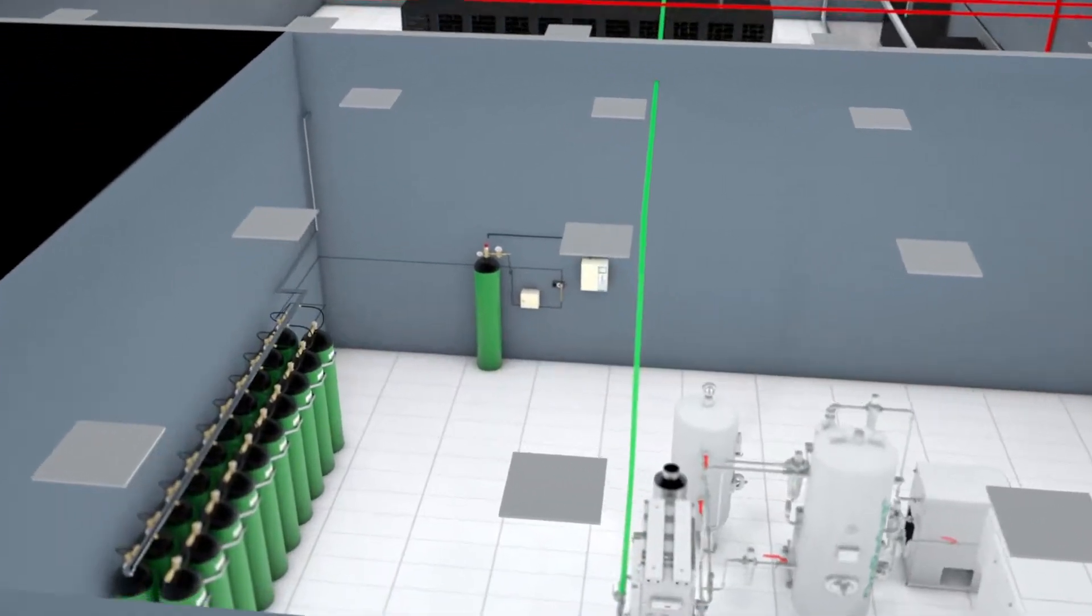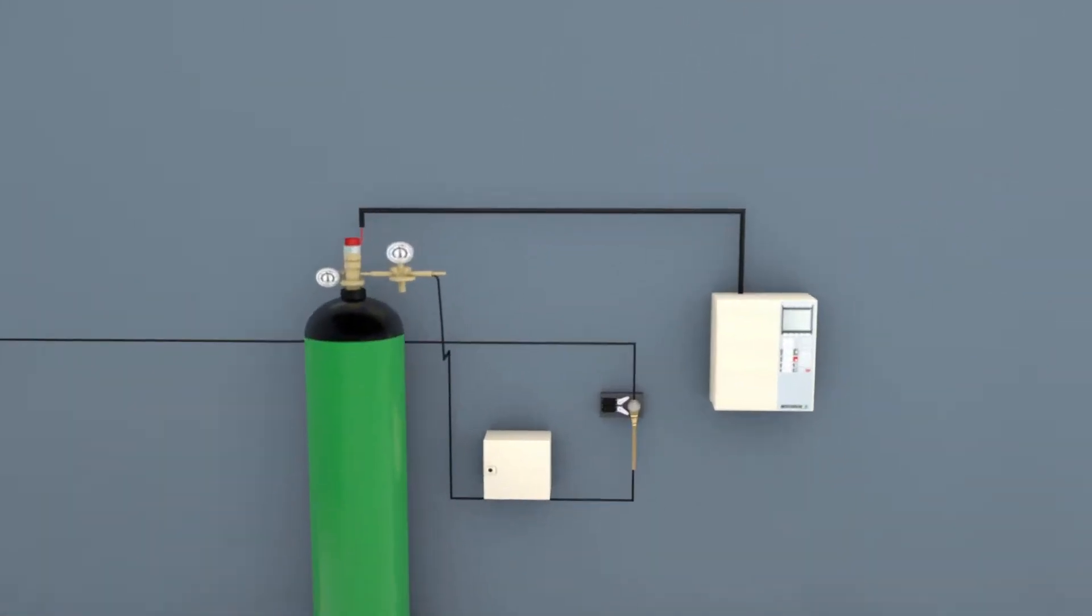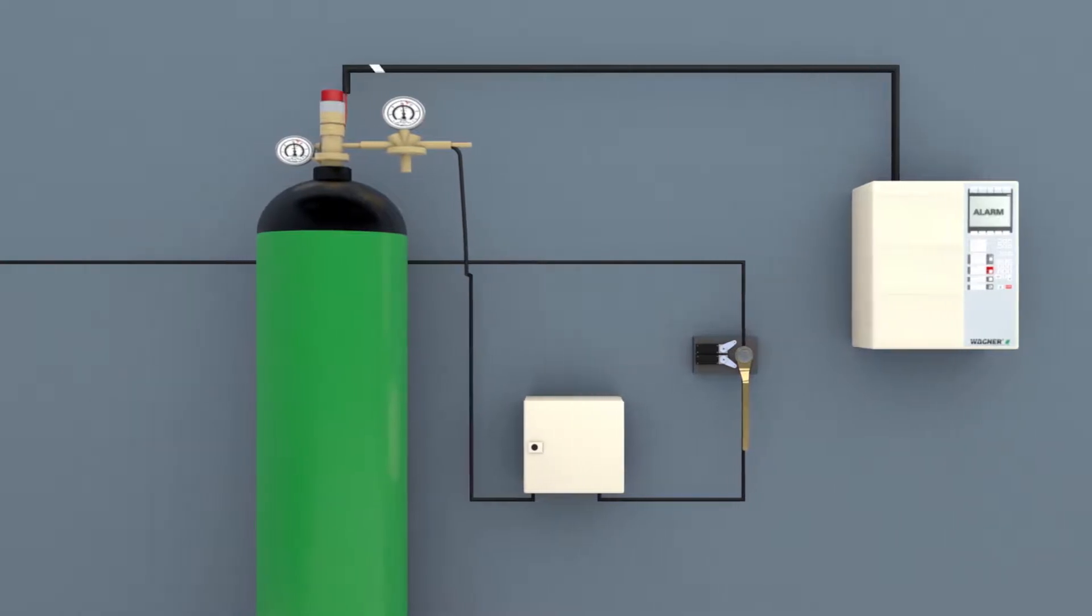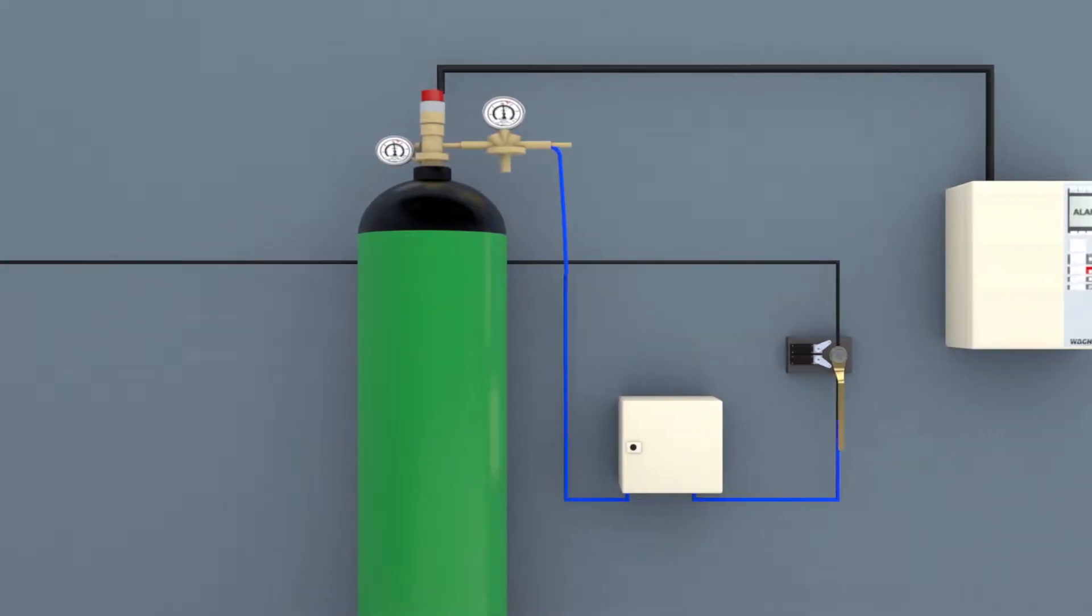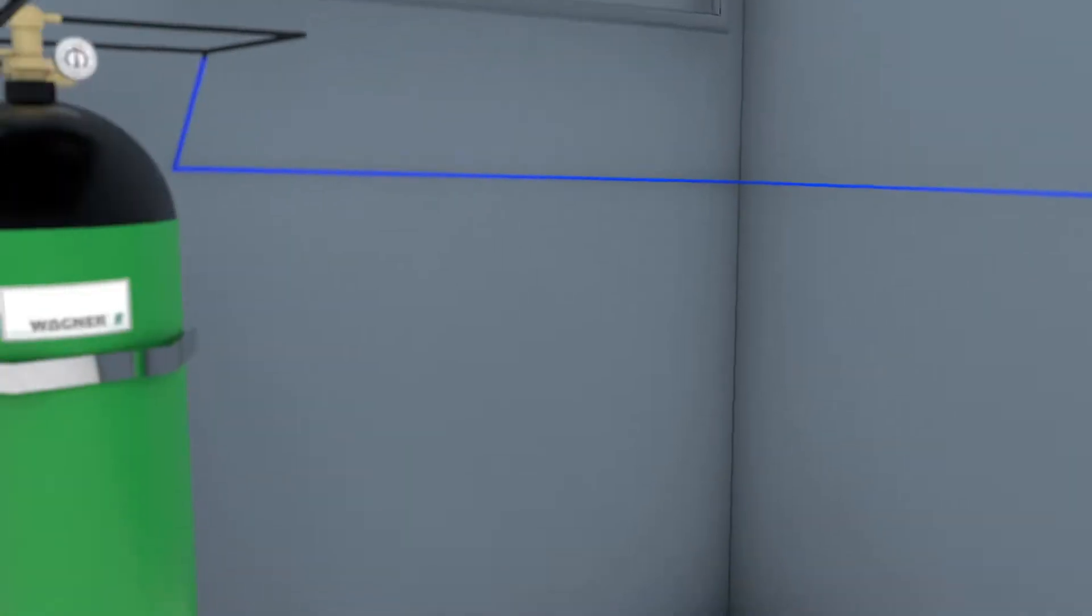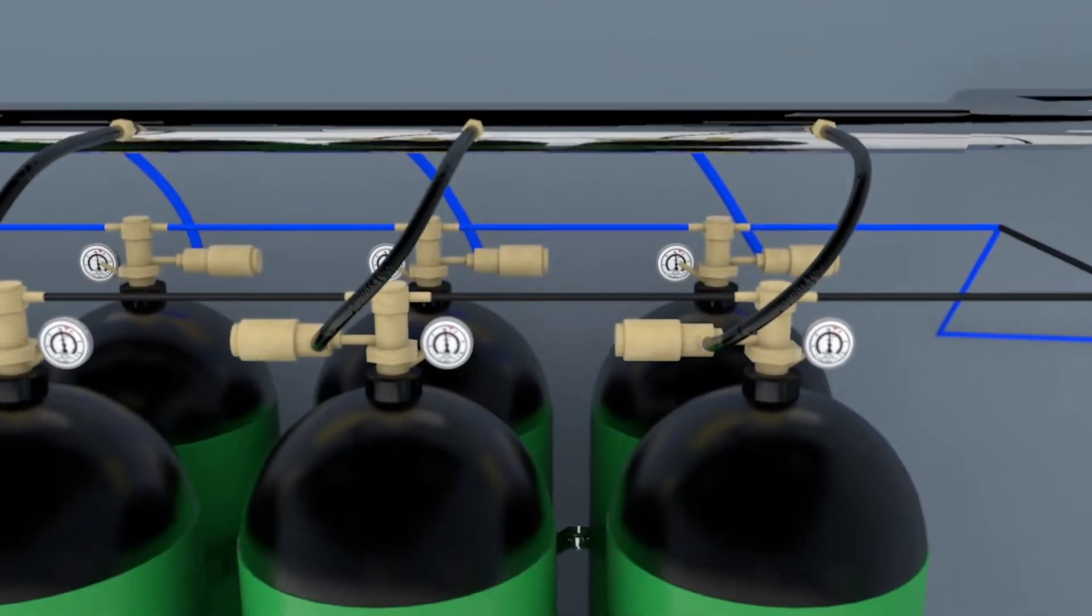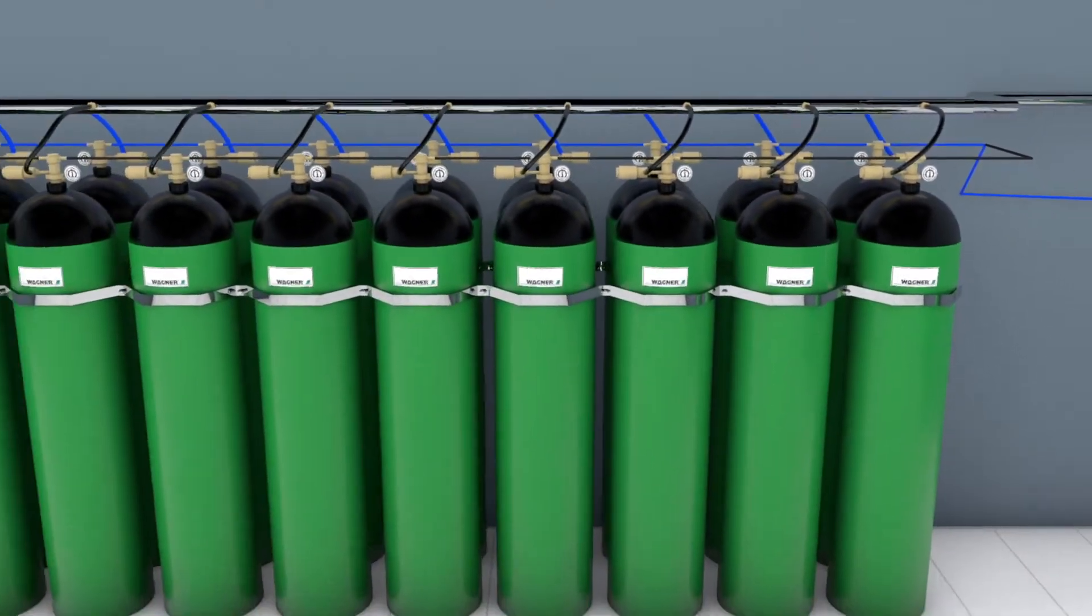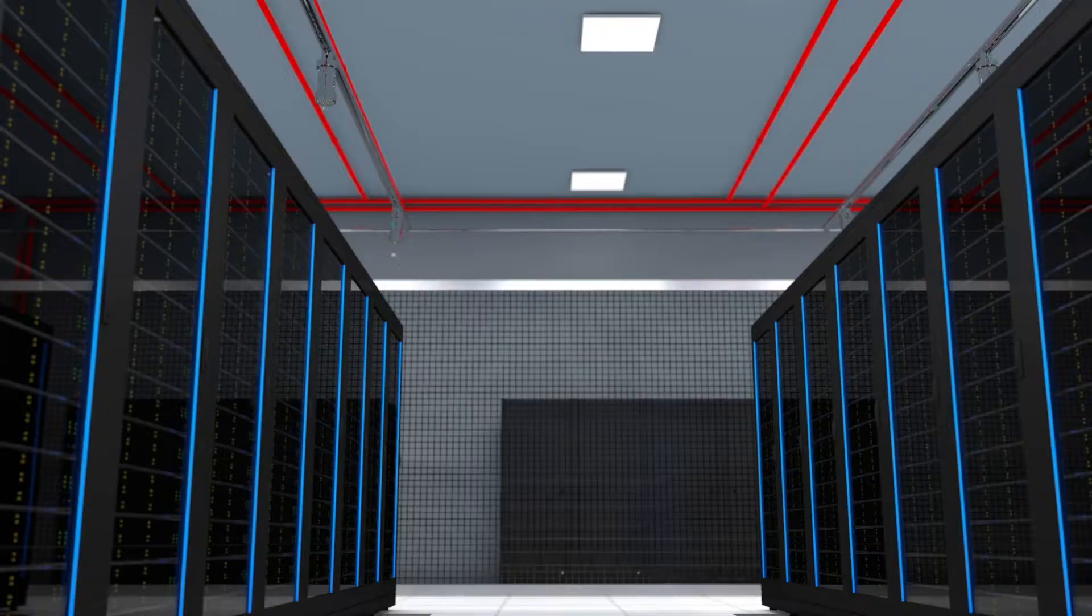Such a significant time advantage means that countermeasures can be taken early. Similar to a fire extinguishing gas system, the oxygen level is immediately lowered from the atmospheric standard of 20.9% by volume to initially 17.0% by volume.